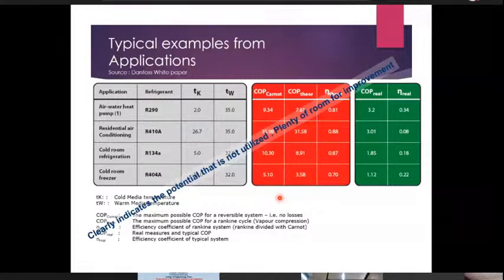So we've undergone one full cycle of change of refrigerant because of ozone layer depletion. And for that reason, HCFCs are now being phased out. So you can see some volume of R22 refrigerators, but most of the air conditioning market has moved to refrigerants which do not have any ozone depleting potential. So R410A, for example, has a zero ozone depleting potential. R32 has a zero ozone depleting potential. So both these refrigerants are being widely used in air conditioning products in the market today.